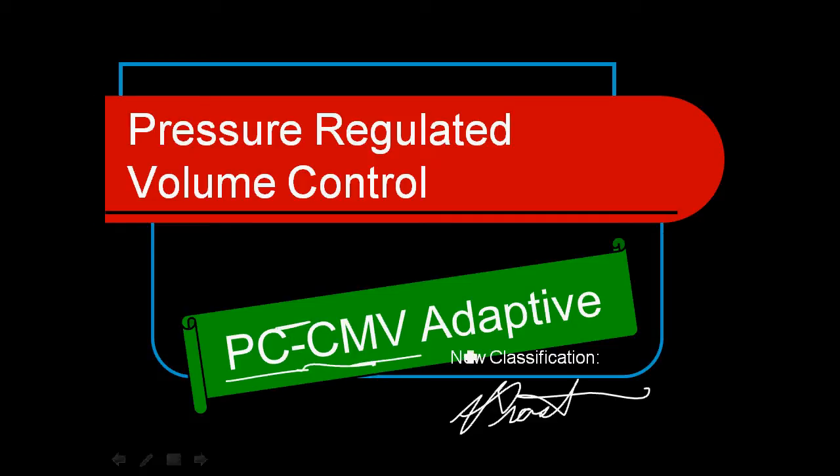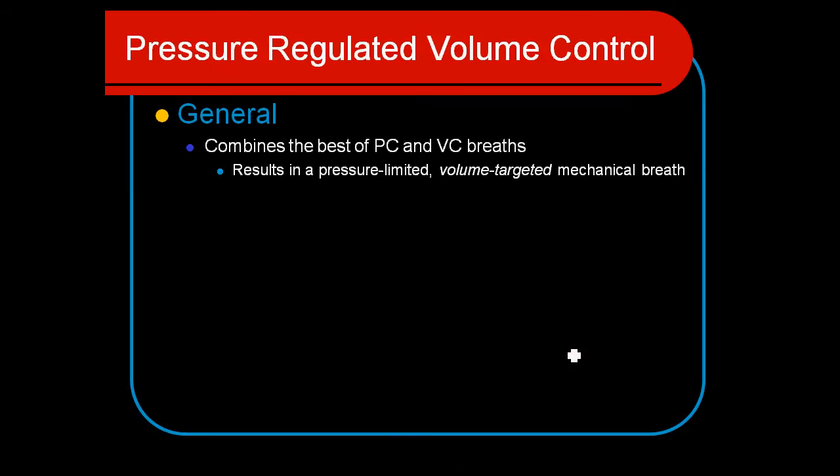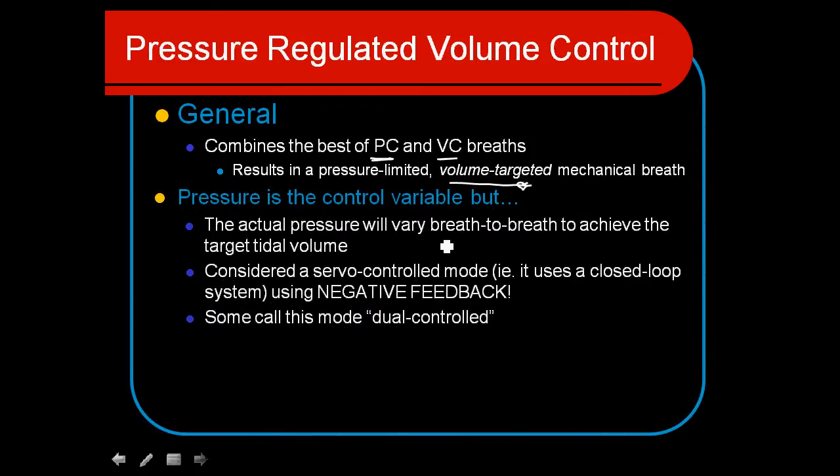PC-CMV — and the key word here is adaptive. It adapts to the patient's lung characteristics. This mode combines the best of both pressure control and volume control. The uniqueness of this is that we get a set targeted volume, just like with volume ventilation, but we also get the benefits of the flow characteristics and the changes as it adapts to the patient's efforts with pressure control ventilation.